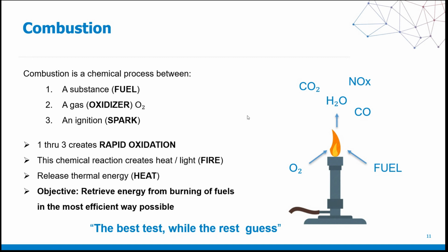And what we're trying to determine is if it is meeting those certain acceptable benchmarks of health, i.e. oxygen percentage being normal, CO2 percentage being normal, CO ppm being normal. So if we're not performing a combustion analysis, we can't just tell by looking at an appliance how healthy it is. We actually have to delve a little bit deeper and actually do an analysis.